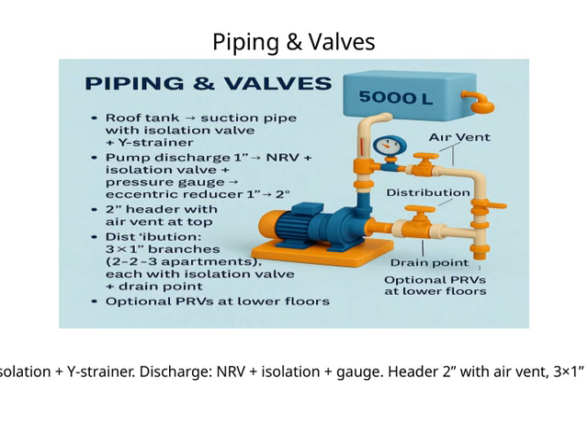Let's take a closer look at the piping and valves setup here. On the suction side, we have an isolation valve paired with a Y-strainer. This combination is crucial because the isolation valve allows us to shut off the flow for maintenance, while the Y-strainer helps filter out debris to protect the system. Moving to the discharge side, we've got a non-return valve, or NRV, along with another isolation valve and a pressure gauge. The NRV ensures flow only moves in one direction, preventing backflow and safeguarding system integrity. The header itself is 2 inches in diameter and is equipped with an air vent to release trapped air, which is vital for maintaining efficient operation. From this header, there are 3 branches, each 1 inch in diameter, allowing us to distribute flow effectively to different parts of the system. Connecting all these components thoughtfully ensures reliable operation and ease of maintenance, which ties directly into our overall focus on system efficiency and safety.